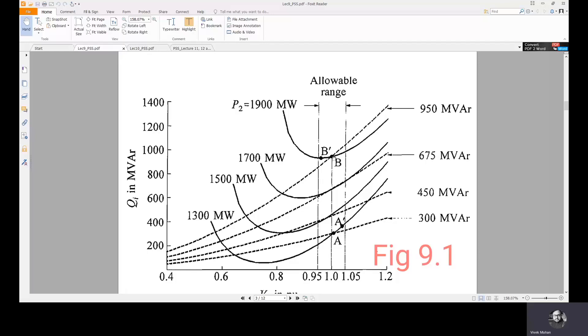At a higher load range, at 1700 megawatts, the capacitor characteristic is almost tangent to the system characteristic, meaning the slopes are nearly equal at the intersection point. When the loading level is further increased, the slope of the capacitor characteristic exceeds the slope of the system characteristic — this becomes an unstable point, whereas the lower loading level intersection points are stable.